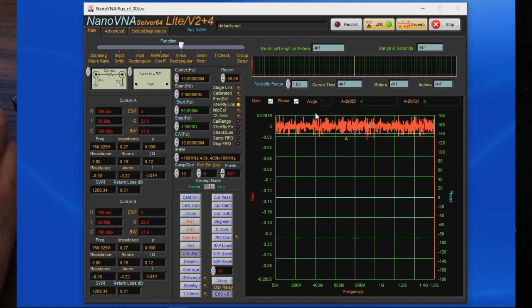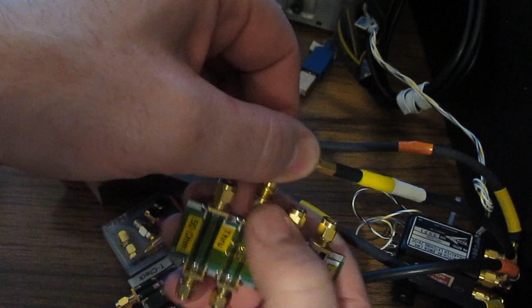So now let's replace the through with our 20 dB attenuator. You can see with normalization, at 50 kilohertz, it's reading 20.01 dB. Of course, as we move up in frequency to 1.5 gigahertz, it gets all the way up to 17.8 dB. But let's turn off the normalization, and now you can see how the phase wraps around. You can see we're all the way down at minus 23 dB, all the way up to 21. So I guess the question is, is the error the attenuator? Maybe it's in our calibration or our normalization.